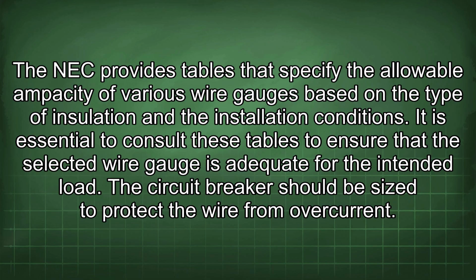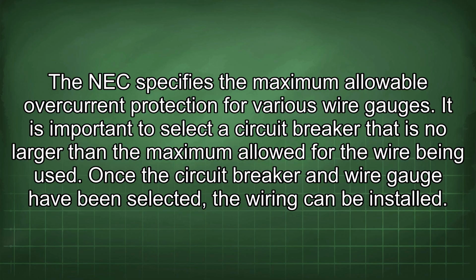The NEC provides tables that specify the allowable ampacity of various wire gauges based on the type of insulation and the installation conditions. It is essential to consult these tables to ensure that the selected wire gauge is adequate for the intended load. The circuit breaker should be sized to protect the wire from overcurrent. The NEC specifies the maximum allowable overcurrent protection for various wire gauges. It is important to select a circuit breaker that is no larger than the maximum allowed for the wire being used. Once the circuit breaker and wire gauge have been selected, the wiring can be installed.